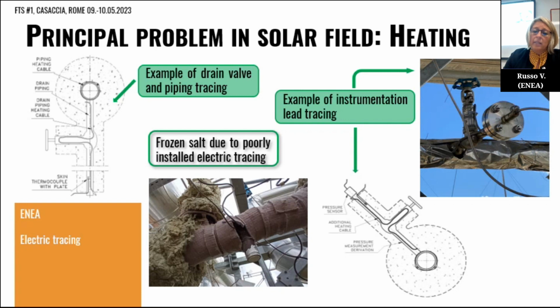Here this is a picture of a draining pipe inside with molten salt solidified inside. This happens because the tracing was not properly installed. Here instead there is a scheme of the tracing of an instrumentation line, like for example a pressure sensor or a temperature sensor. In this photo it is a pressure sensor.